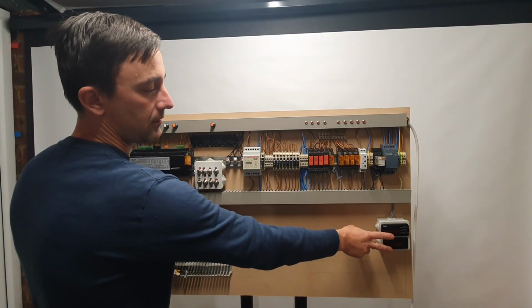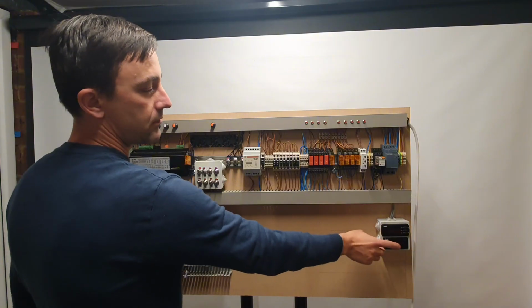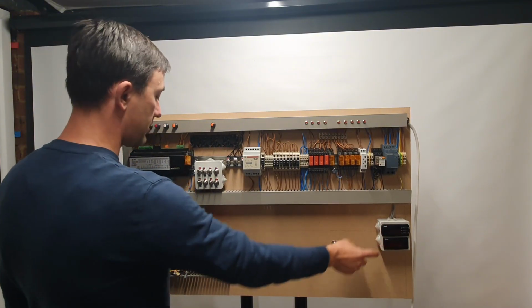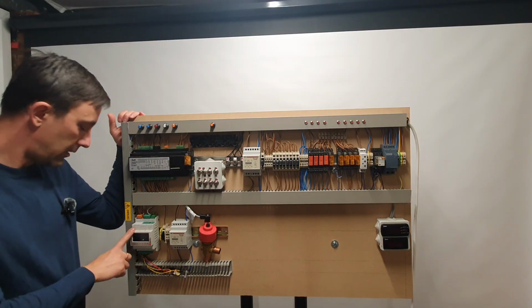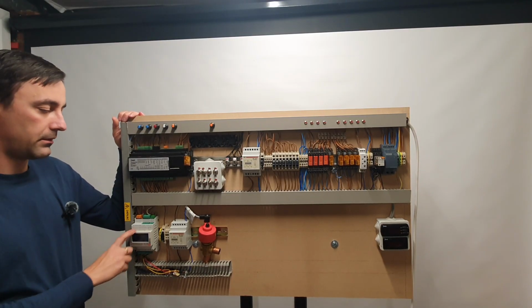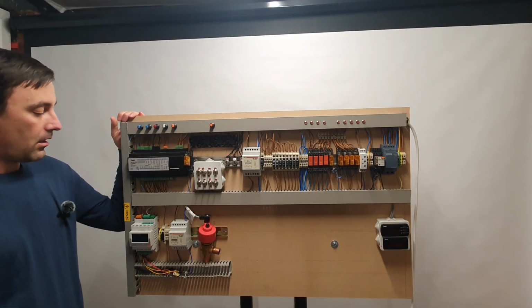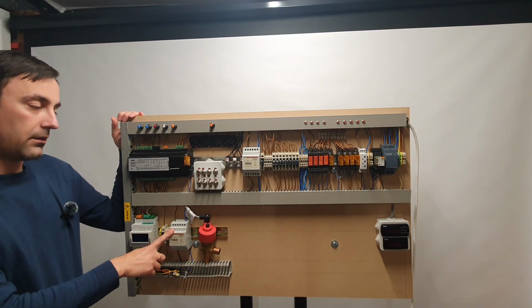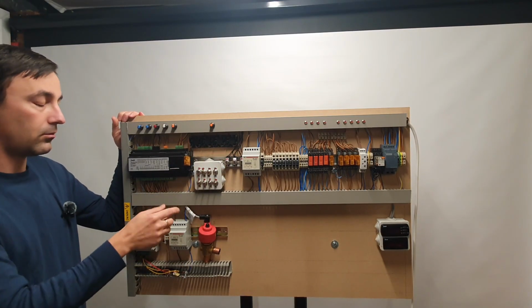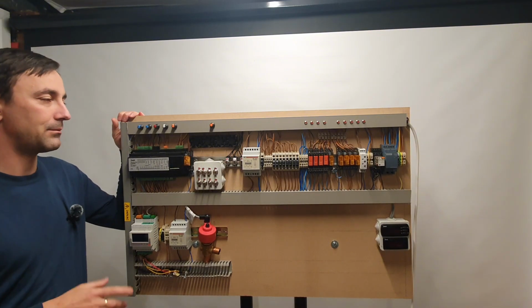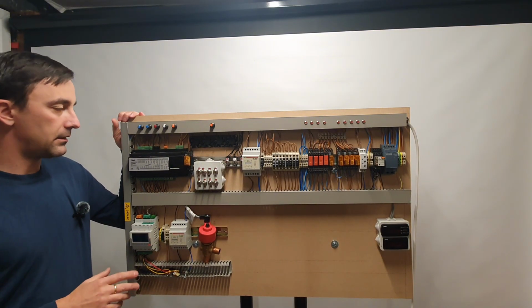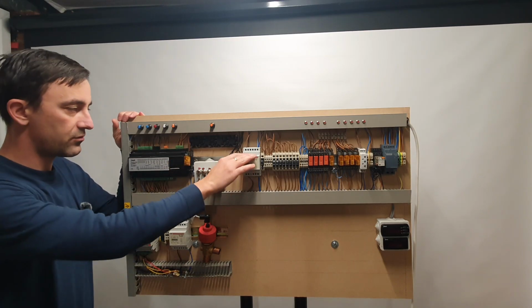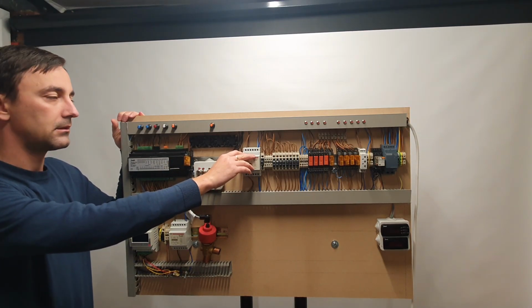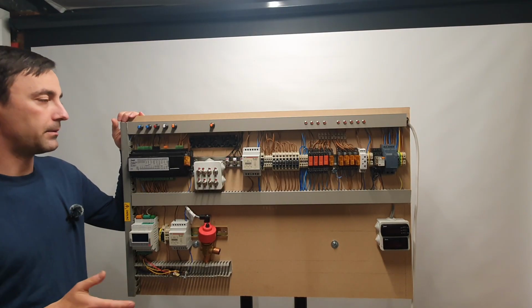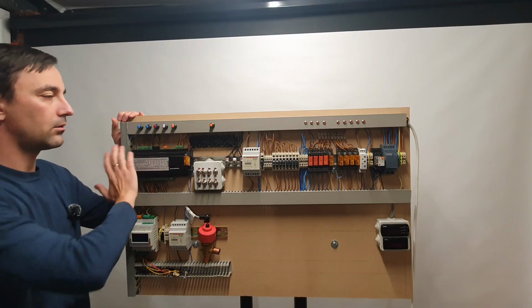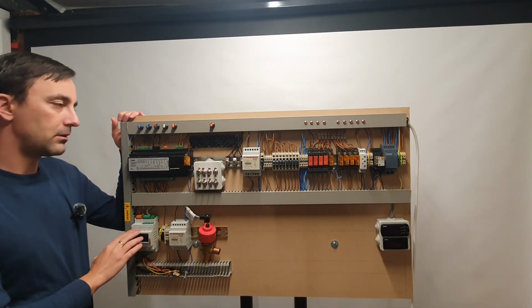We have our display, suction pressure and discharge pressure. We have our EVD twin controller. These controllers can operate a stepper valve, just like this one. Now you might see another transformer here, and you might wonder why haven't you used only one transformer. Well, I did initially, and I made a big mistake, because this transformer was overheating. And I was a bit baffled. I said, why is that happening? There should be enough for one transformer to run all of this, including that one. Well, I couldn't be more wrong.